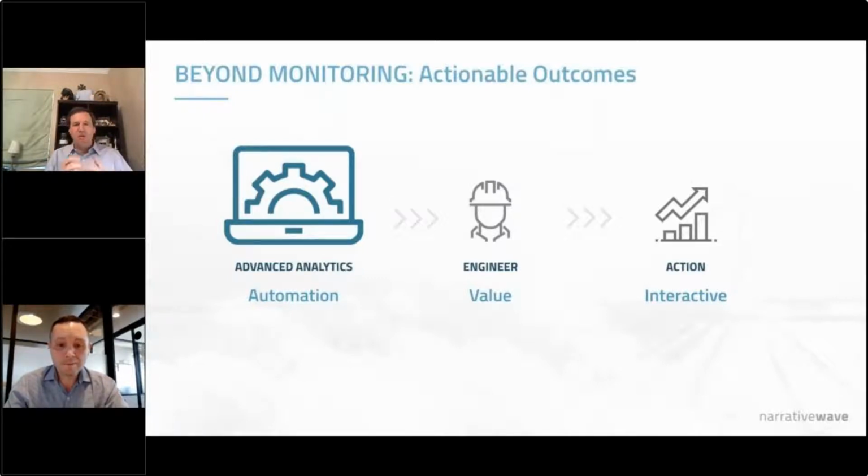Johnny, can you talk us through some examples of this at a high level? What does that look like when we've shifted the focus from the engineer to an automation approach using analytics? Yeah, you bet. So let's start with what an engineer might do in an example. Consider a failing or a failed fan in an inverter cabinet. When this is happening, the engineer is having to check the temperature of the cabinet over time, seeing it rise, right? Manually looking at the data potentially or dealing with an alert. Then they're going to be looking to correlate that rise in temperature to a decrease in performance, eventually getting to availability issues on that individual asset, right?